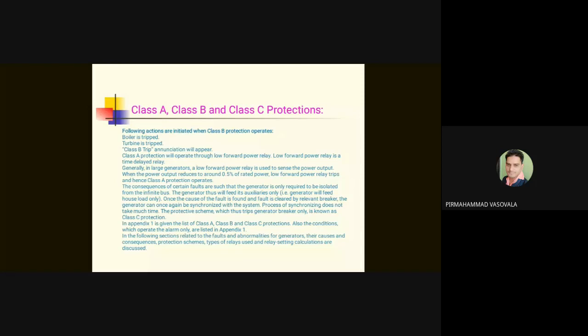Not only the rotor parts of the generator, but the rotor parts of the turbine as well, because you might be knowing well that the generator rotor is run by three stages of turbine: the HP stage, the IP stage, and the LP stage. So all rotor parts would be accelerating. This we are avoiding in class B. So this is what is happening in class B trip.